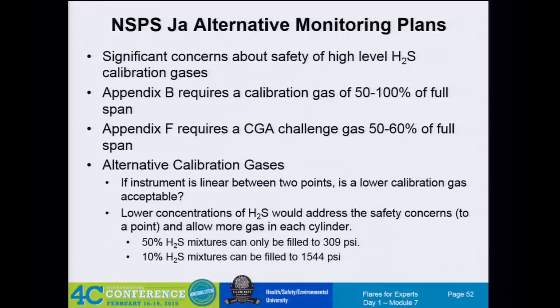Okay, I guess that's my question, is if you do some other process to remove it ahead of that. Yes, it's what's that analyzer going to see, because that analyzer is measuring the gas going to the flare tip. So if that flare gas is treated before it gets to the flare tip and before it is seen by that analyzer, then it's like it was never there.